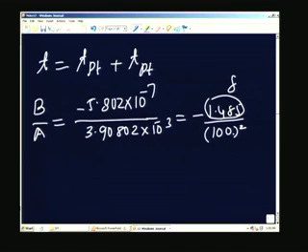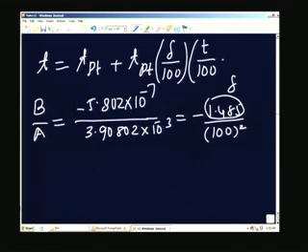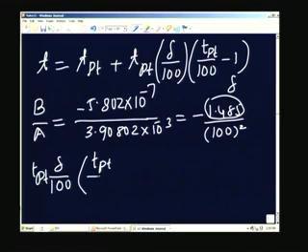Therefore, delta divided by 100 squared is B by A. And if I now go back to that expression, the correction will become simply delta by 100. You can verify that T by 100 minus 1, and I am going to approximate it by T PT by 100 minus 1. So, this factor delta by 100 multiplied by T PT multiplied by T PT by 100 minus 1 is called the C, the calendar correction.